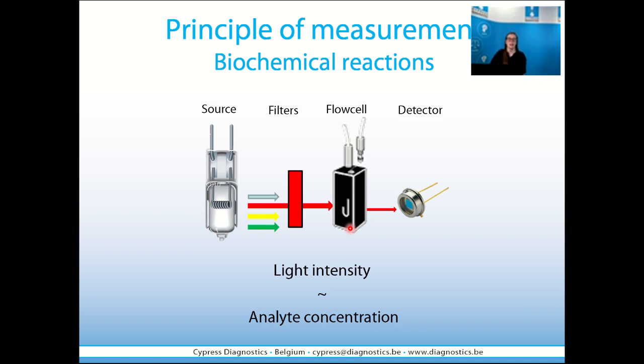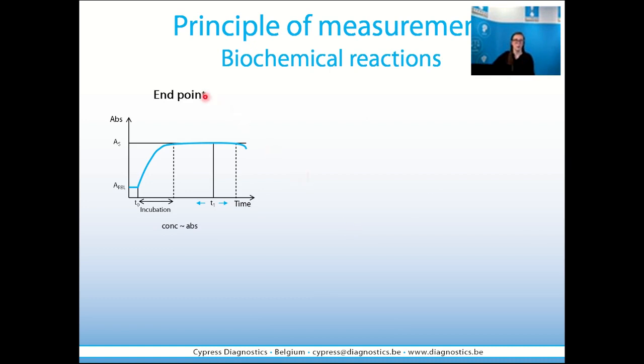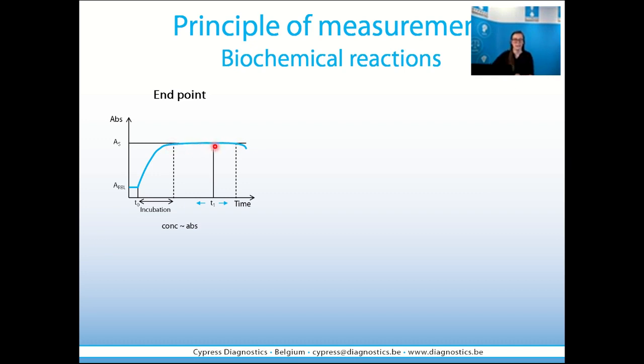There are three biochemical reactions we would like to discuss. The first one is an endpoint reaction. When no sample is added to our reagent, we have a very small absorbance. At time zero, when sample is added to our reagent, you will see a sudden increase in absorbance. Specifically for endpoint reactions, we will see that the color reaction will stabilize. It is at this time point that we will measure the absorbance of the sample. The concentration of the analyte will be calculated with this absorbance.